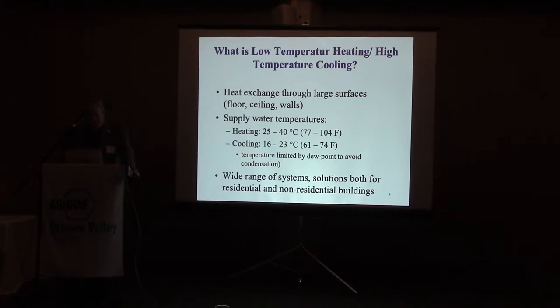So what we are talking about for heating is temperatures in the range 25 to 40 degrees centigrade. In modern low energy buildings, it's even lower. And for cooling, for most of the radiant system, we are talking about a range from 16 to 23 degrees. So you see, they're pretty close to the room temperatures that we want. And there are many systems that we call radiant heating and cooling, and I'm going to talk a little about them and some of the basic boundary conditions, the limitations, and give several examples of buildings from around the world.